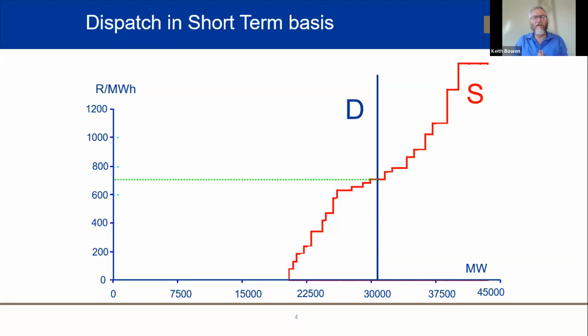We always schedule against demand. In this graph, when we stack all the marginal costs in merit order, we get the supply curve for the industry. Notice the supply curve doesn't start at zero, mainly because of minimum generation points. With large coal power stations like at Eskom, there's a point below which you'll never schedule a generator, its minimum stable generation point.